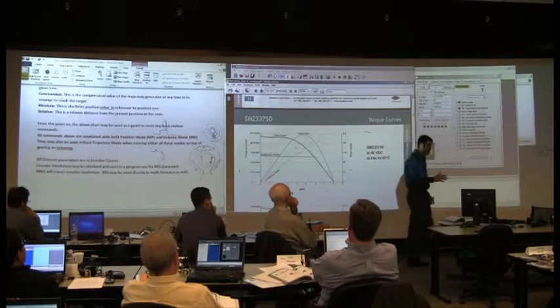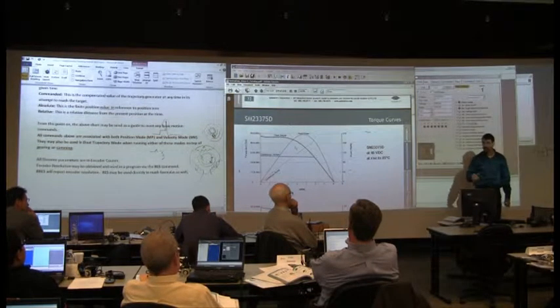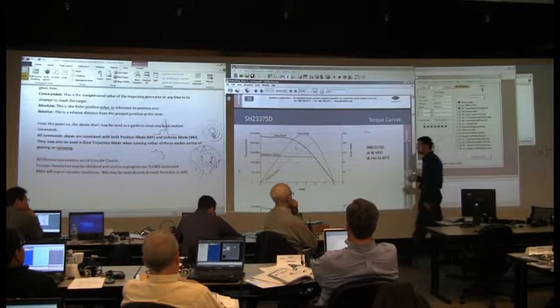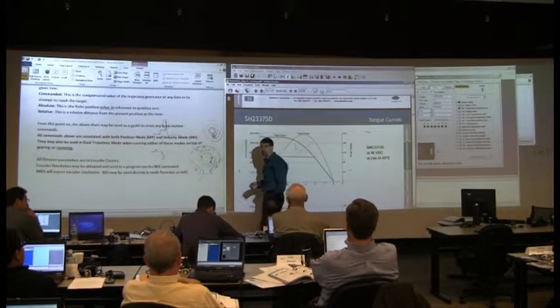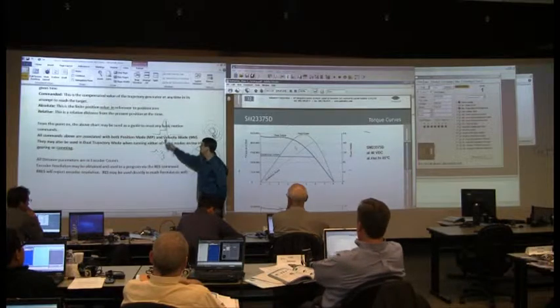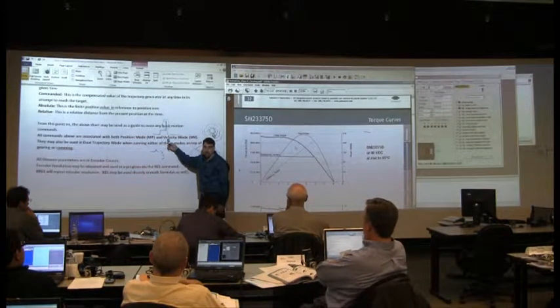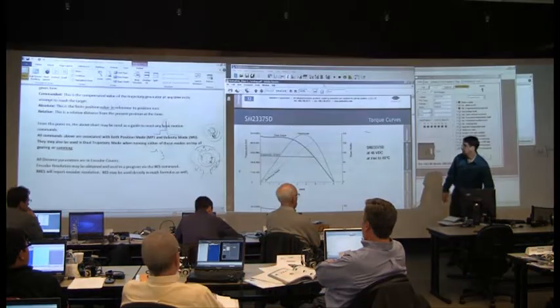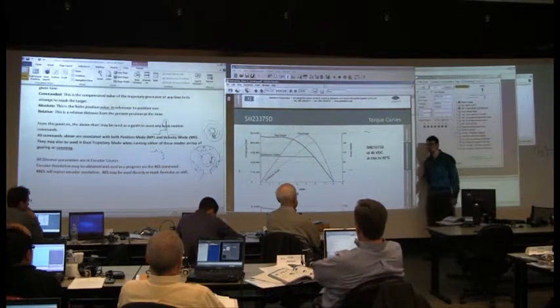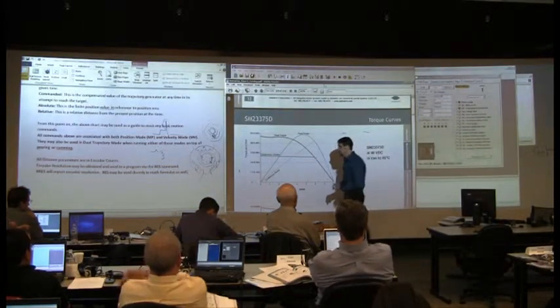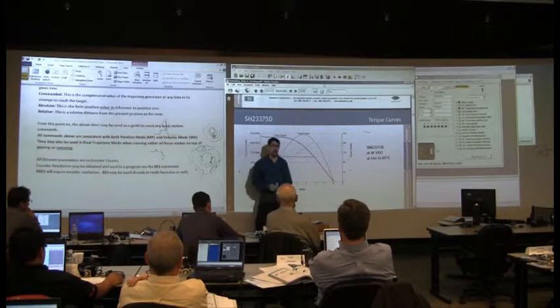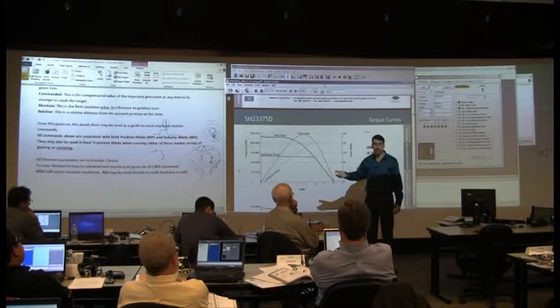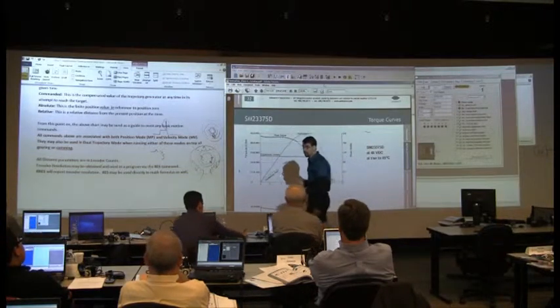There's a rule of thumb that says voltage, or back EMF, is proportional to speed. The voltage is proportional to speed at back EMF. Well yeah, it's proportional to, but it's not equal to. Because if that were the case, when you open the switch on this coil, it would just drop to zero. The worst it would do is stay at 24, but not go beyond 24. But in fact, a small relay coil can go to a thousand volts. Well, it's not spinning fast. This motor can be spinning extremely slow. And I think when Dan was talking to these guys, they said they weren't going that fast at all. And yet its voltage was going well above its voltage constant for the motor.